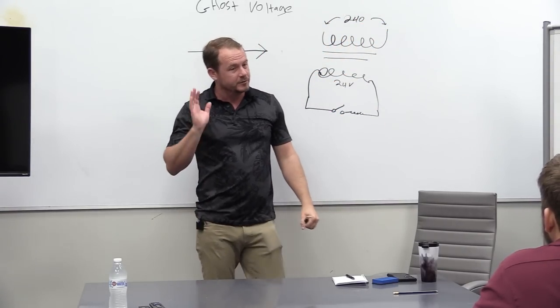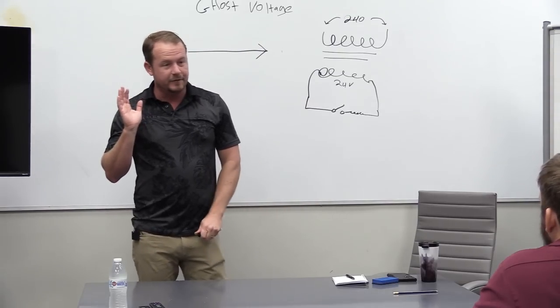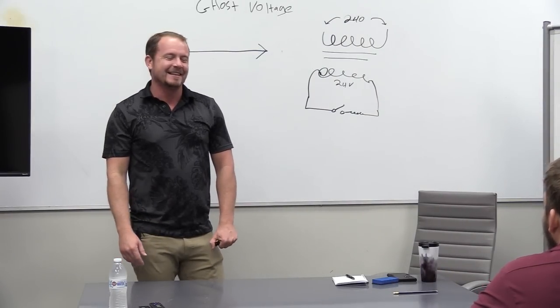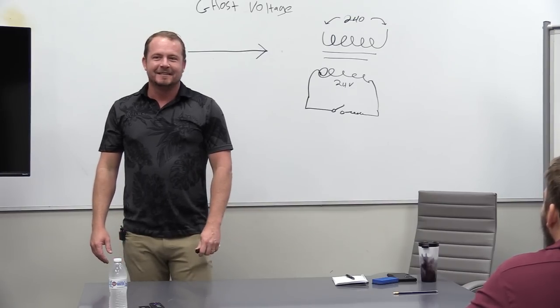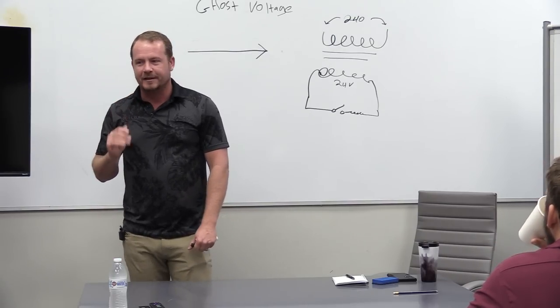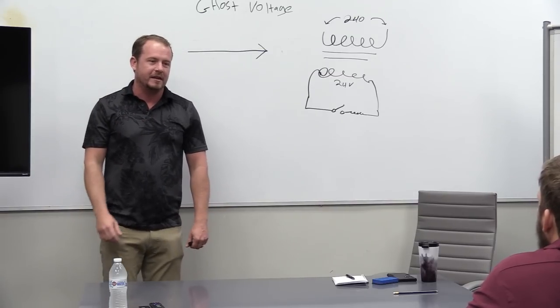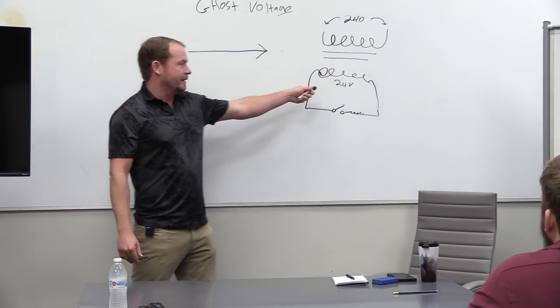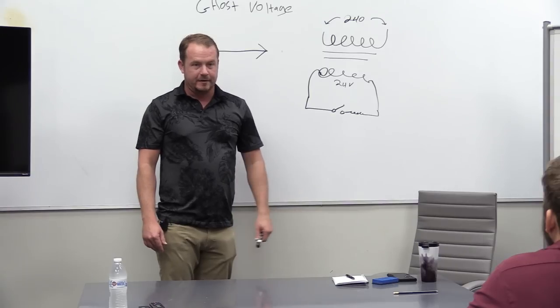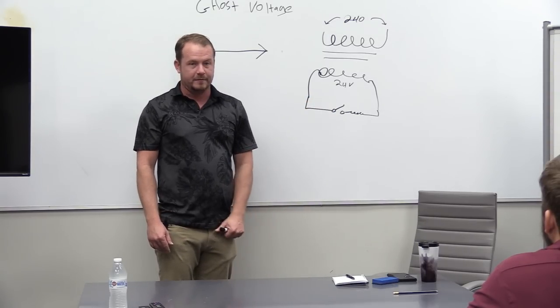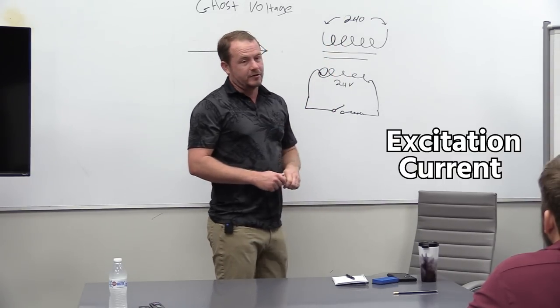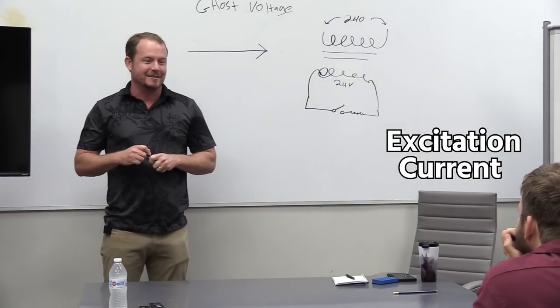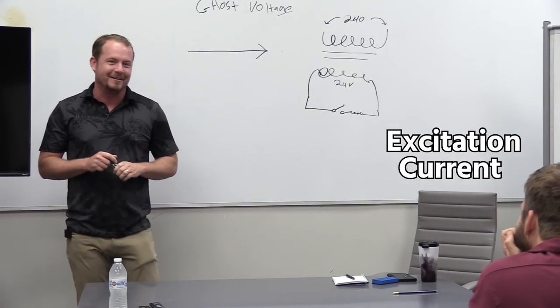This is connected to 240 volts through a coil. If you ever listened to a transformer, even when nothing's running, what's it sound like? Hmm. That's the ghost in the transformer. It makes a little hum, right? You'll hear it humming. If you feel it, you can feel a little bit of heat there. And that's true even if you don't have any load on the secondary, even if there isn't any current moving through the secondary. This is called excitation current.